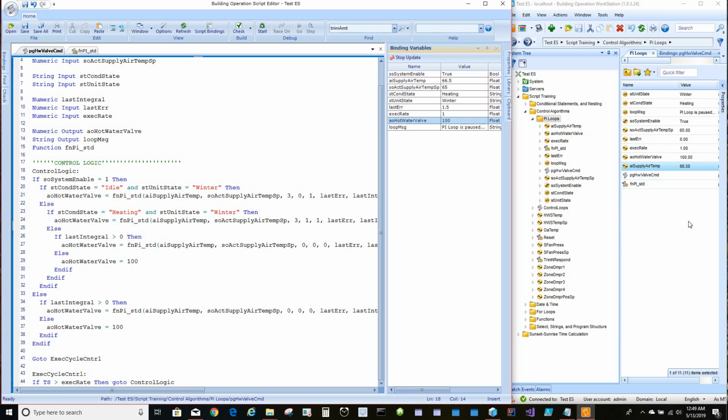See how we've been a while now at 100%. We've been paused for quite some time. If the integral would have continued to accumulate, it would take at least as long for the loop to get back in control.